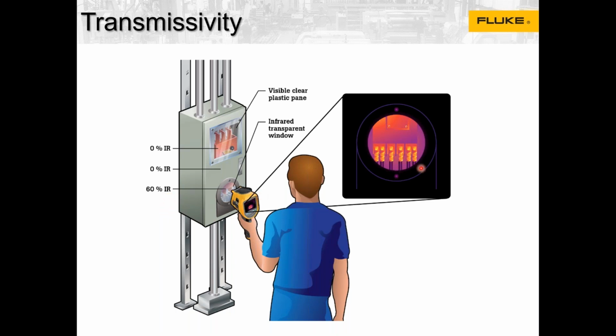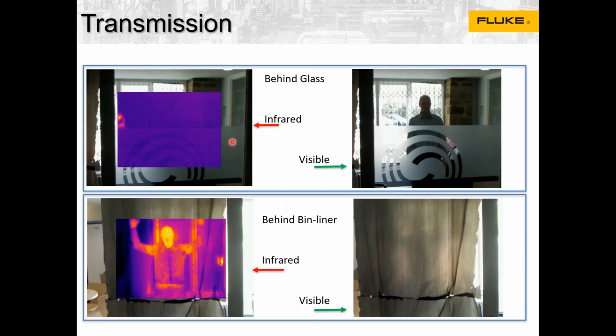Here you can see the internals of your panels. Of course, if you're using wide angle lenses, you can inspect the full panel. So keep in mind, guys, if you have a plexiglass, you cannot inspect the hotspot. You need to remove this plastic pane or plexiglass in order to make your inspection.